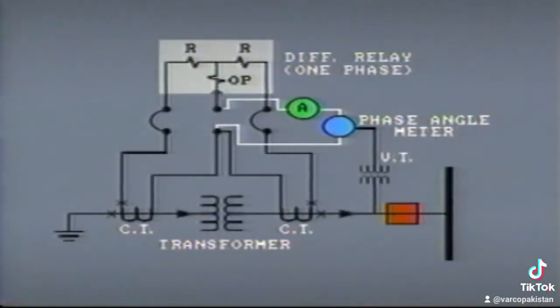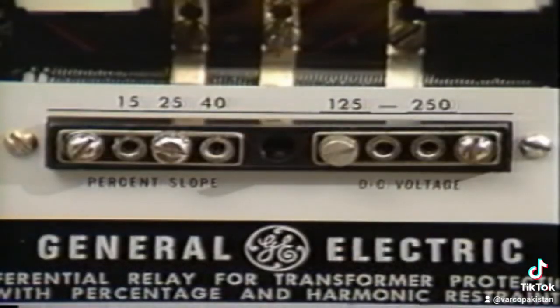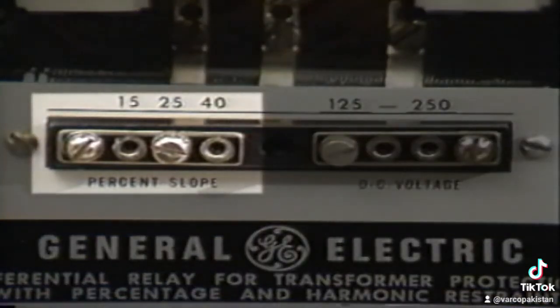But in this case, we should expect to see some current passing through the operating coil. As we pointed out in an earlier videotape, this error current or spill current is due primarily to the selection of transformer taps, plus the effect of dissimilar CTs on either side of the transformer. Obviously, the ratio of spill current to restraint current as measured during the test should be lower than the differential setting of the relay.